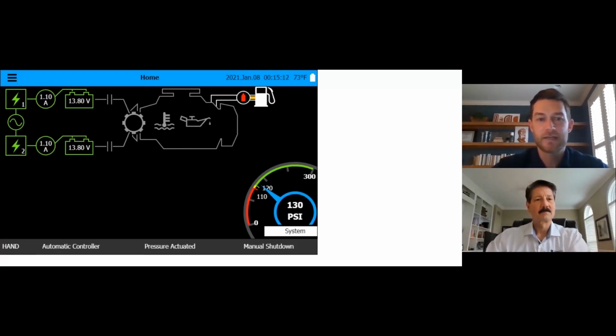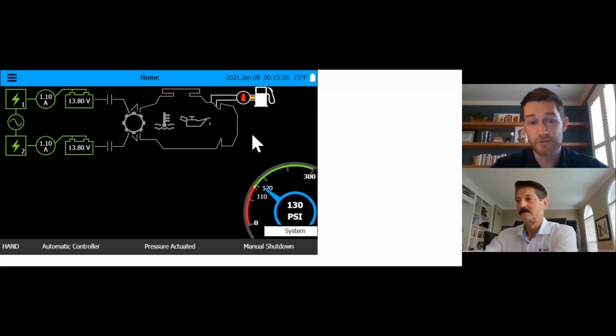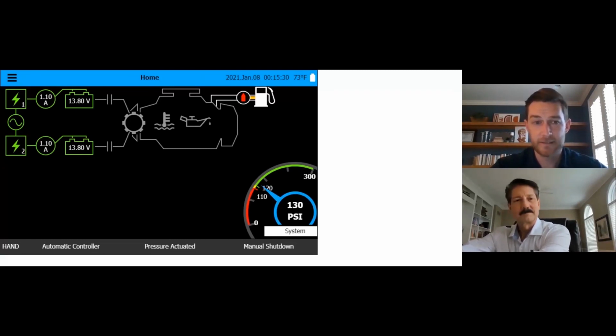So it'll try 3 times from each side before it eventually gives you a fail to start. But that's what those two lines signify. It just shows you visually on the screen which battery bank it's pulling the power from. You actually can do, if you push for a manual start, if you push the numbers 1 and 2 at the same time, it'll pull in the power from both batteries at the same time. That's in an emergency kind of need. If your batteries are drained, you can pull power from both and hopefully get the engine started with that.